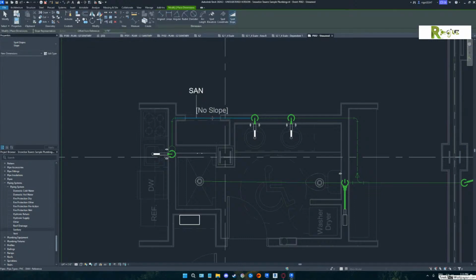You would just put it on the pipe? Yeah, but notice what happens. No slope. They haven't sloped their pipe. Go ahead and hit another one just to verify that they haven't sloped any of it.